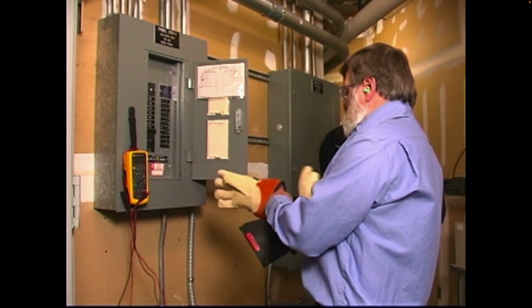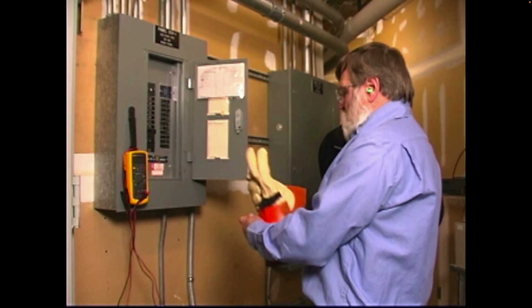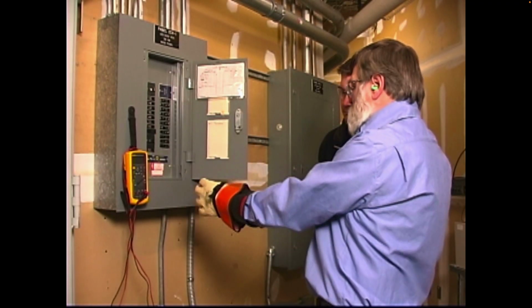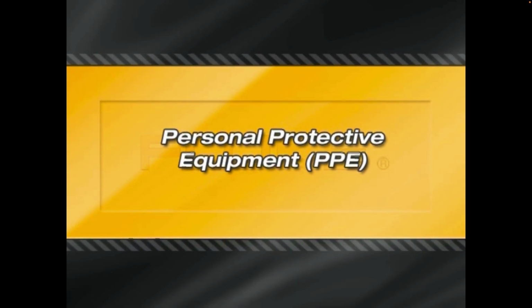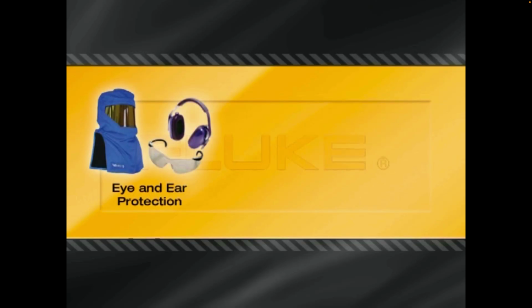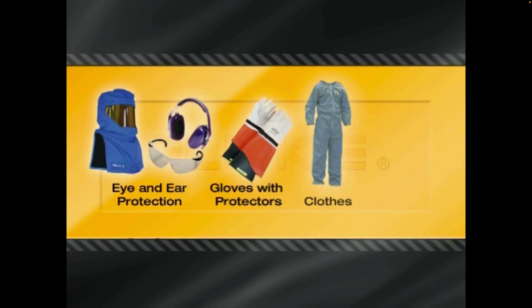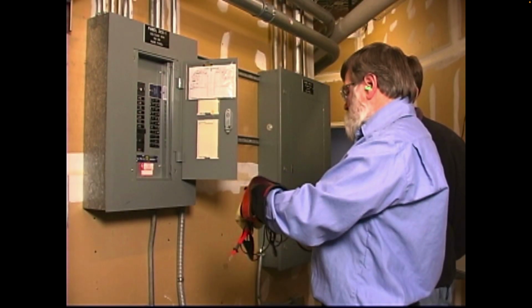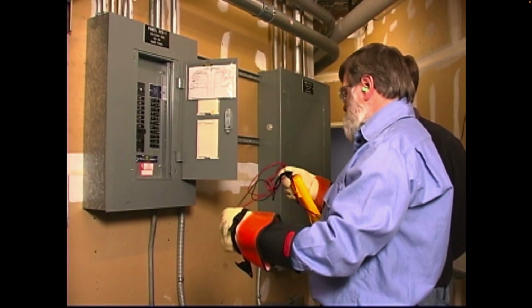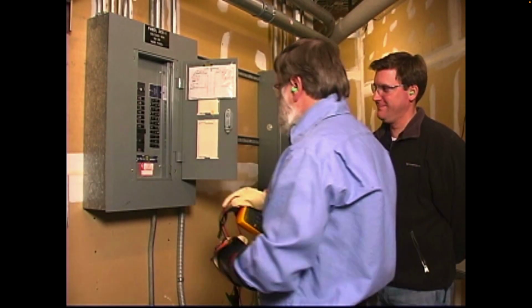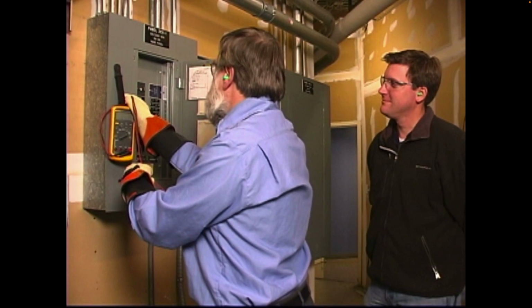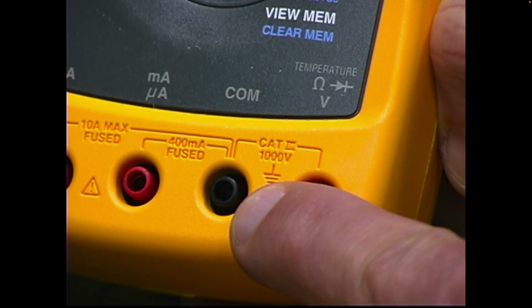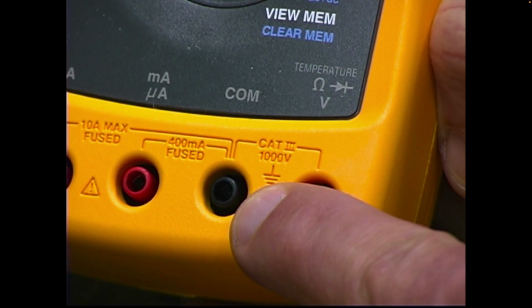Another key part of planning is choosing your safety equipment, tools, and assistance. Make sure you have the required personal protective equipment, or PPE, on hand: eye and hearing protection, gloves, clothing, and insulating mats. Be sure to inspect your equipment to make sure it's in good condition. Check your tools for proper insulation, and make sure your meters and testers are rated and tested for the level of hazard that exists where you're working.